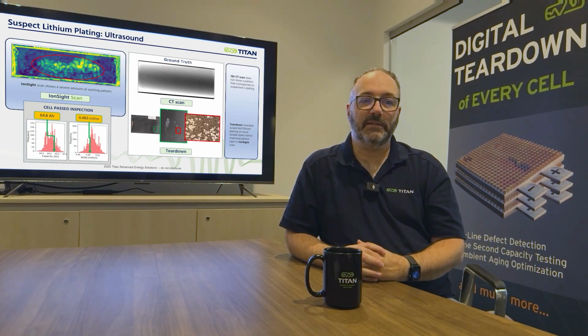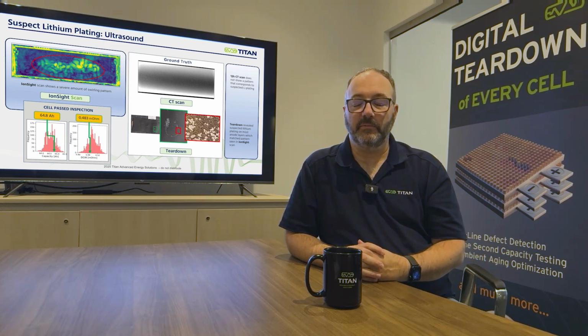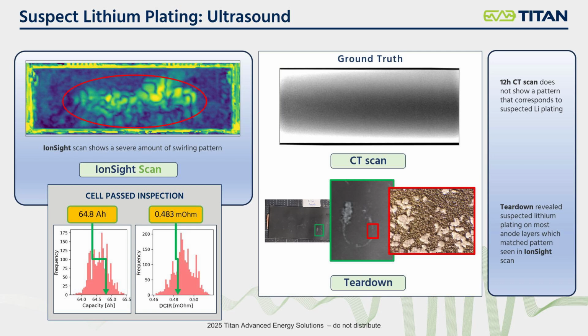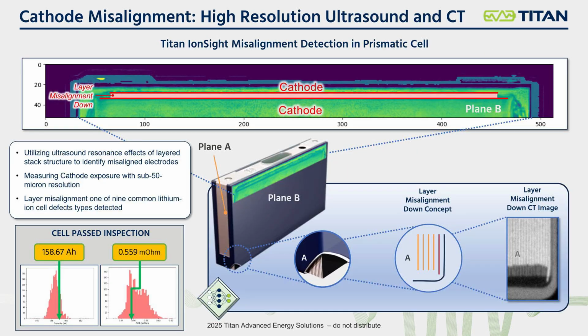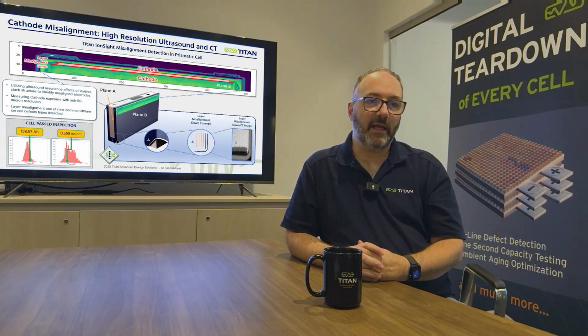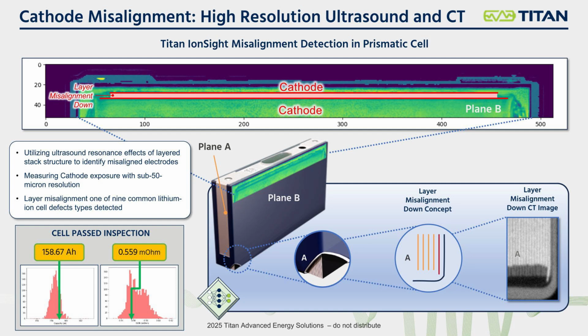So one of the last slides to think about is that we not only do prismatic cells, we work on pouch cells, and in the next quarter or so, we'll be coming up with a new system that is handling cylindrical cells. And over here we see clear lithium plating in a pouch cell, and you can see again that swirling, what we call the swimming pool pattern, is a pattern that comes from lithium plating. And this was cathode misalignment down and anode misalignment up. In this case, what we're showing you is basically between a 10 to 40 micron misalignment of a cathode, which you can see in the CT in the bottom right corner. That same battery is represented in the ultrasound in the top part, where we clearly see the misalignment of the cathode.